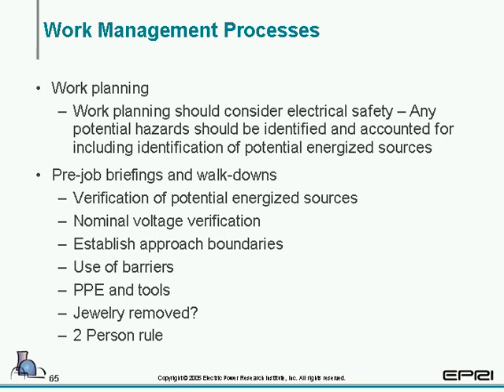Any potential hazards on an electrical job should be identified and accounted for, including that identification of potential energized sources, things such as backfeeds, potential PTs and CTs. Pre-job briefings and walkdowns should identify and verify potential energized sources. Voltage verification, establish approach boundaries, use of barriers, PPE and tools, things like jewelry, is jewelry removed, and discuss two-person rule if your plant has this.